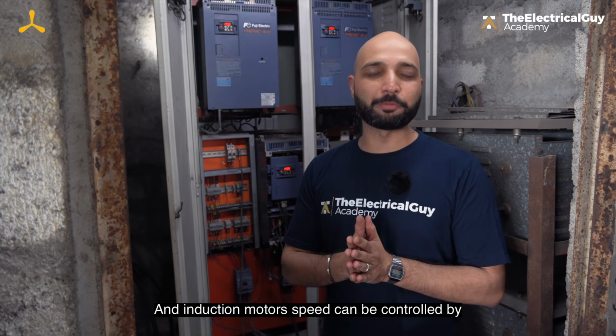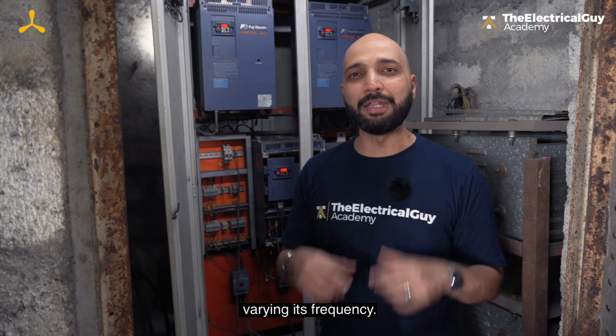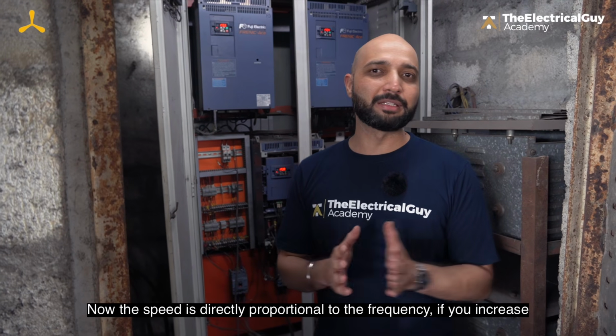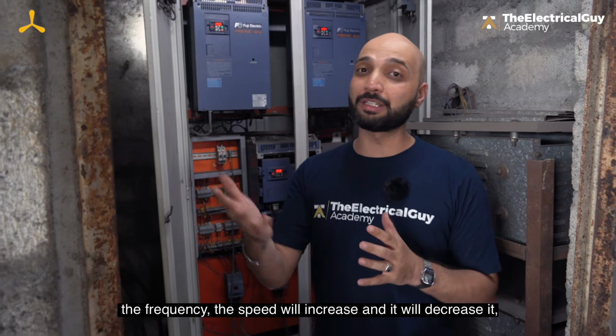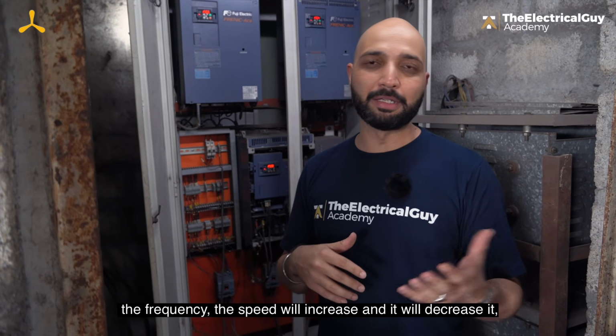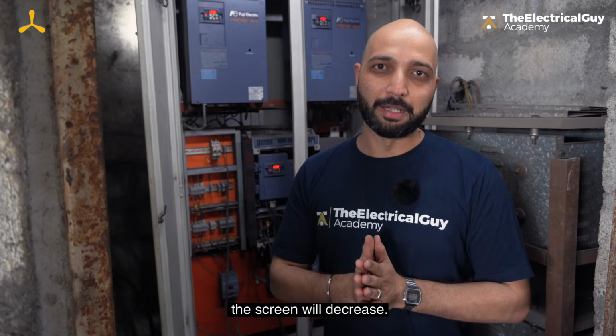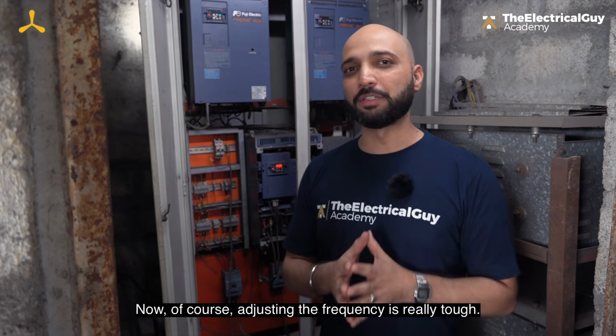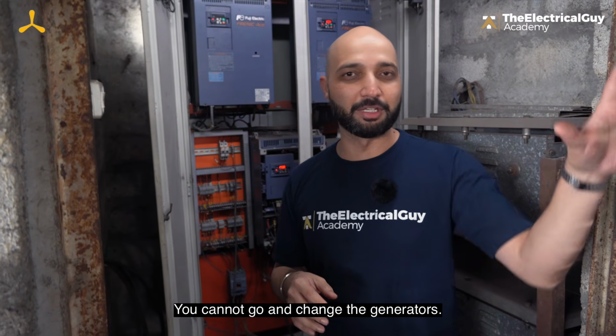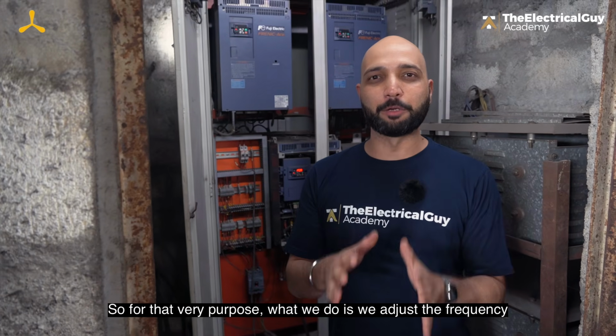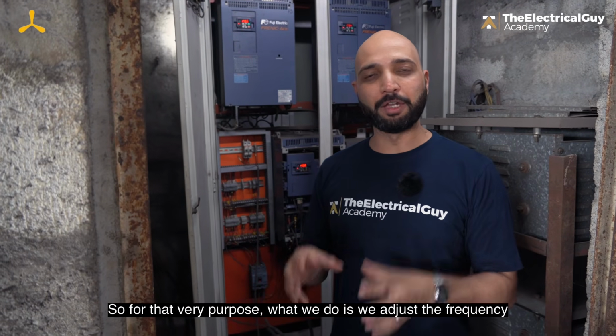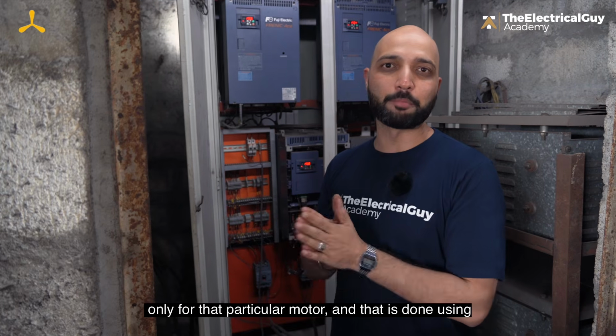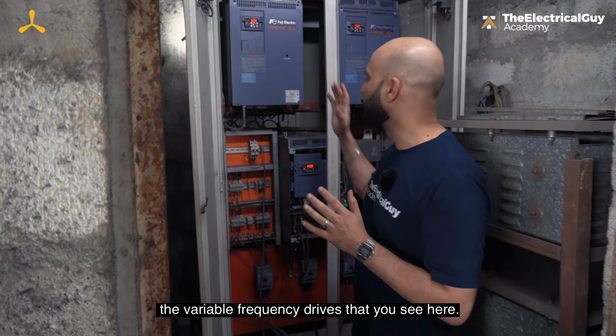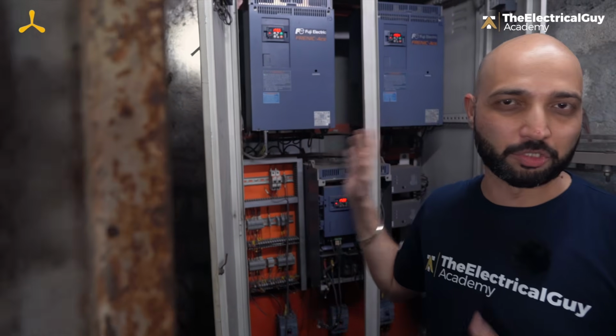And induction motor speed can be controlled by varying its frequency. Now the speed is directly proportional to the frequency. If you increase the frequency, the speed will increase, and if you decrease it, the speed will decrease. Now, of course, adjusting the frequency is really tough. You cannot go and change the generators. So for that very purpose, what we do is we adjust the frequency only for that particular motor. And that is done using the variable frequency drives that you see here.